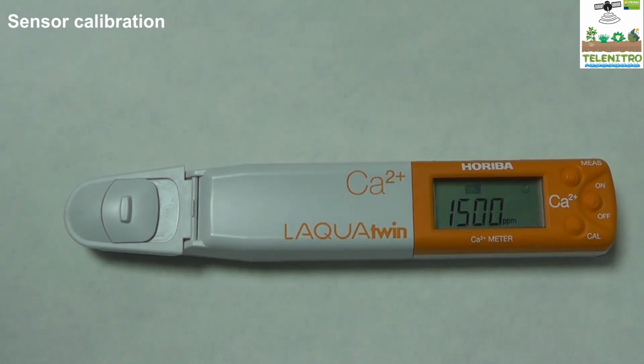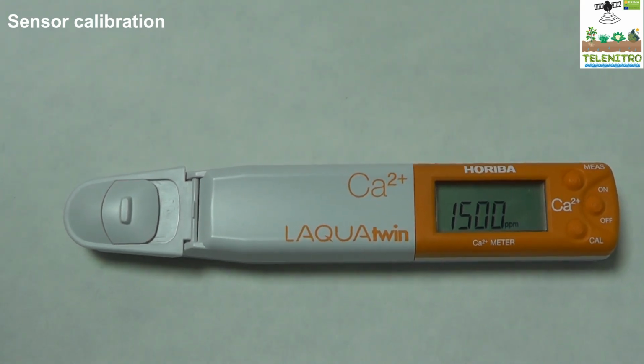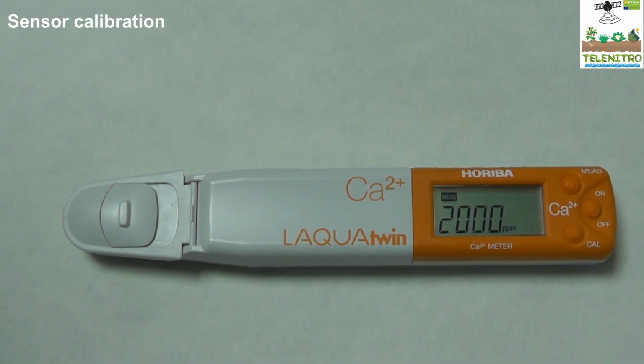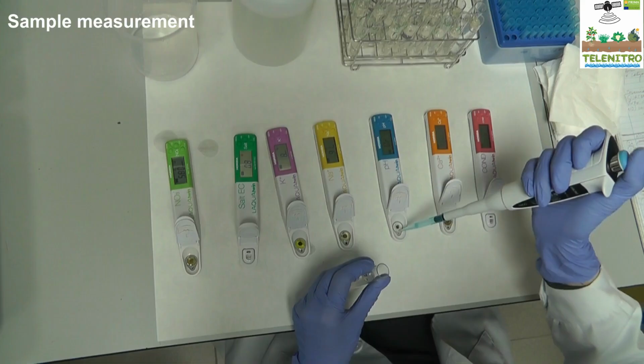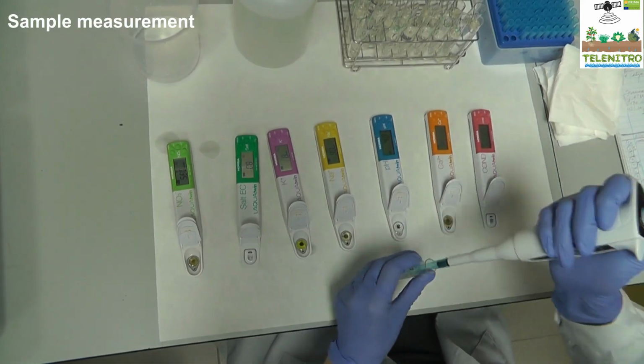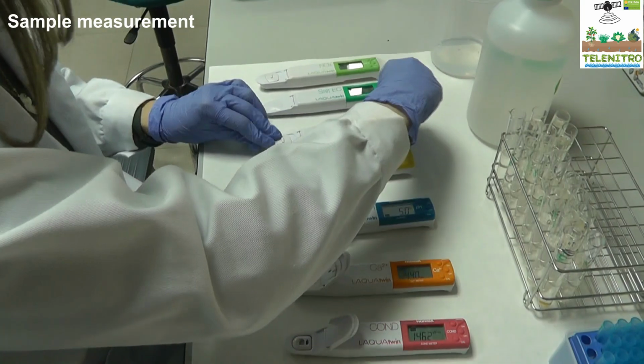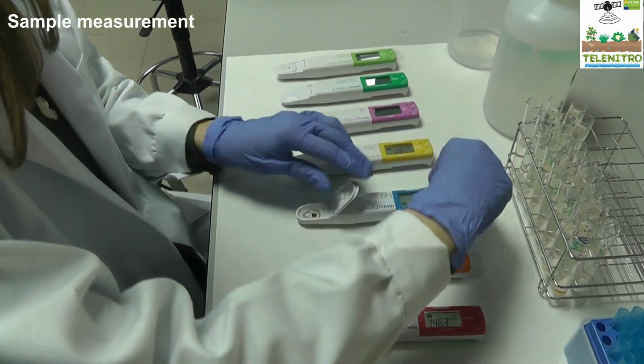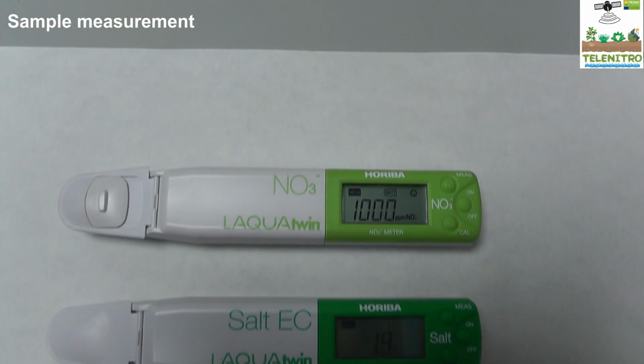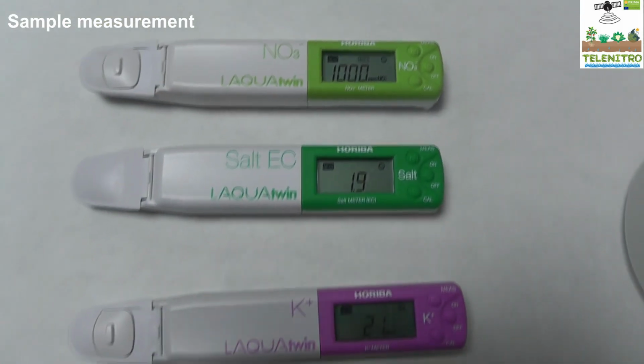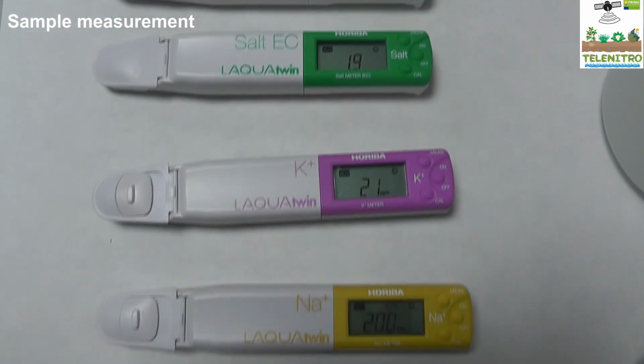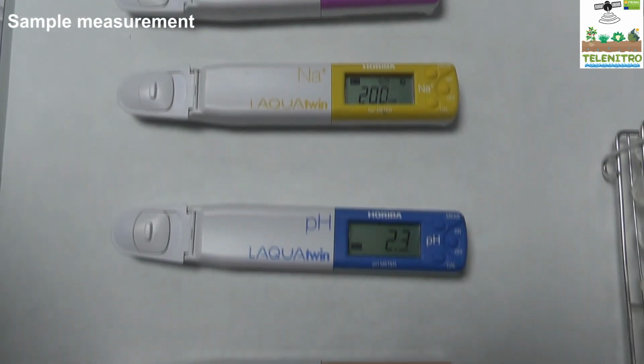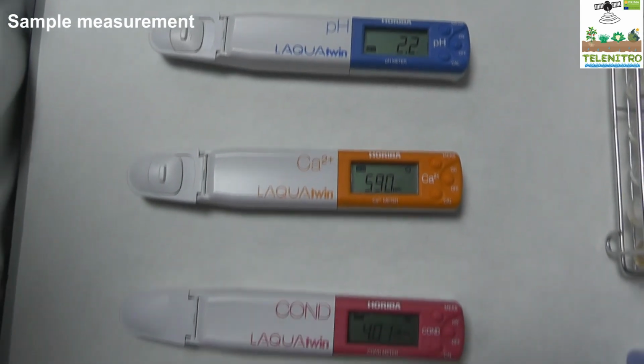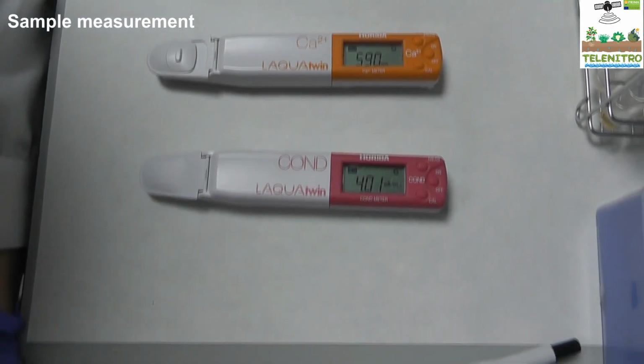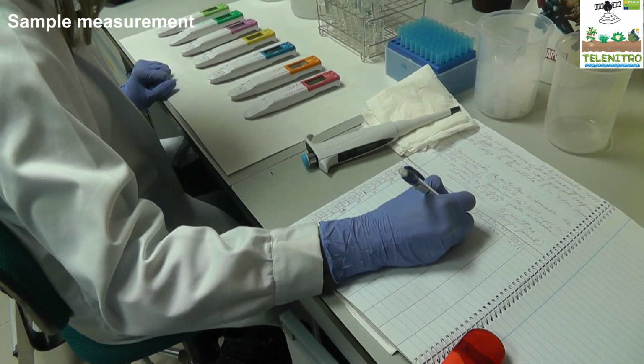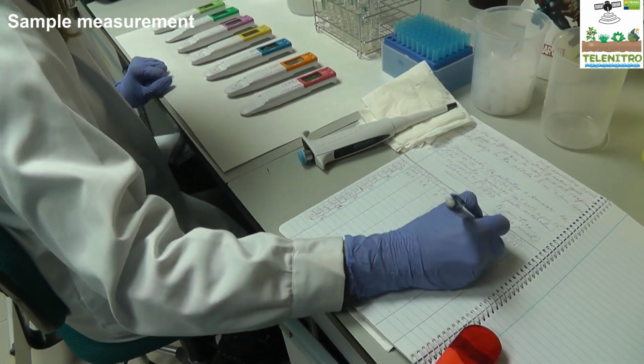After calibration, the MEAS button is pressed to switch from calibration mode to measurement mode. 300 microliters of each sample is placed on the sensor, and the opaque lid is closed before starting the measurement. The MEAS button is pressed for 0.5 seconds to enter measurement mode. The MEAS button will flash until the measured value stabilizes, and the symbol appears continuously lit. This method is followed consistently to calculate the measured parameter.